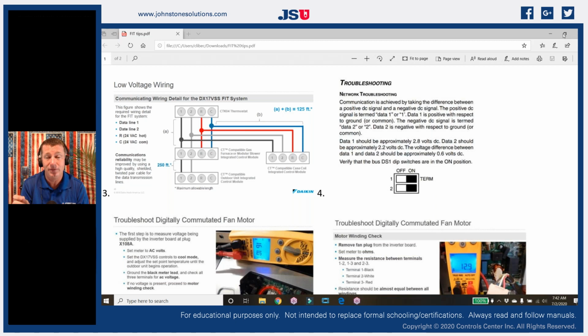When we're talking about 5 volts DC and sometimes milliamps of current, we're talking low voltage and low current. So it's super critical to have proper landing on those number 1 and number 2 terminals, because it has to be able to talk and it has to have a differential voltage of 0.6 volts or higher. On our Daikin equipment, they install a separate terminal called the DS1 switch, the DS1 bus, and it actually helps change the bias. So say I can't change my control wire and I have to reuse that 18-2 solid thermostat wire already running to my outdoor unit. Well, as long as I'm getting 0.6 volts DC bias or above, the system's going to work properly.